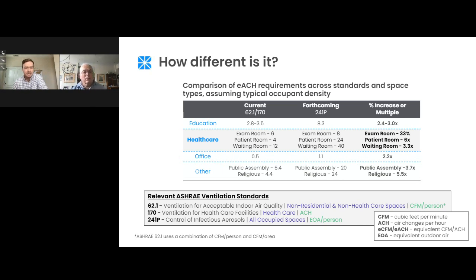And quickly, just to make sure we're on the same page, I'll mention EACH just stands for equivalent air changes per hour. Dr. Nardell, you may want to go into that more, but overall, ASHRAE 170 lists their ventilation targets in ACH, whereas 62.1, which is the standard for non-healthcare environments, lists theirs in CFM, or cubic feet per minute. And the forthcoming standard 241P lists theirs in CFM per occupant, and they describe it as EOA, or equivalent outdoor air, basically air that doesn't have those infectious microorganisms in it.